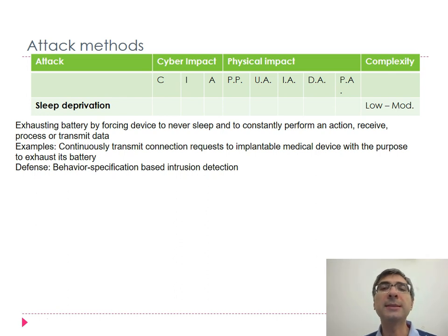If someone, for example, sends a command to an implantable medical device, please give me the latest measurement for this or that, then there is a trust that the medical device is indeed needed by that user, that they actually need to see the sensor value. But in reality, it might be someone who keeps doing this just to keep the implantable medical device busy, and by keeping it busy, exhaust its battery. So that's the point of a sleep deprivation attack. It's about exhausting the battery by constantly performing an action, by constantly receiving, processing, or transmitting data.